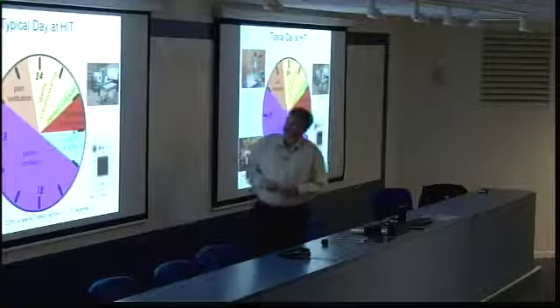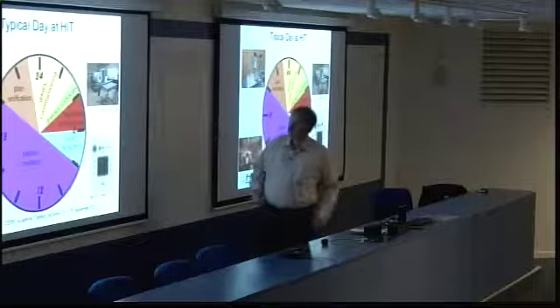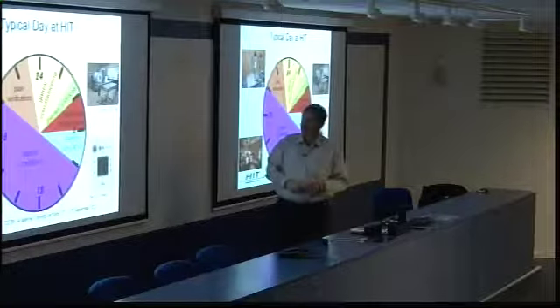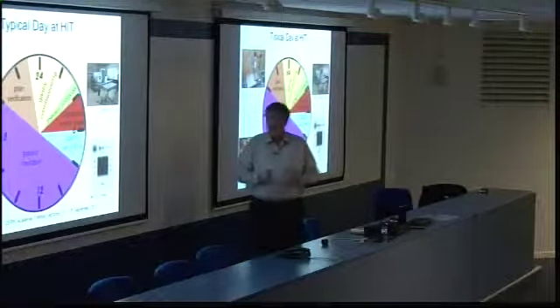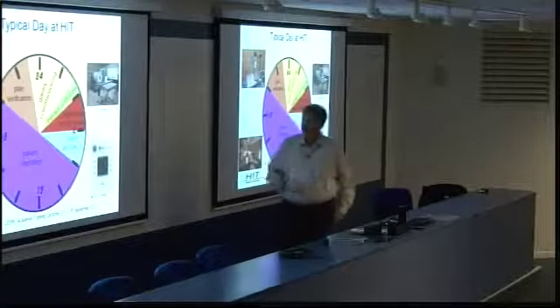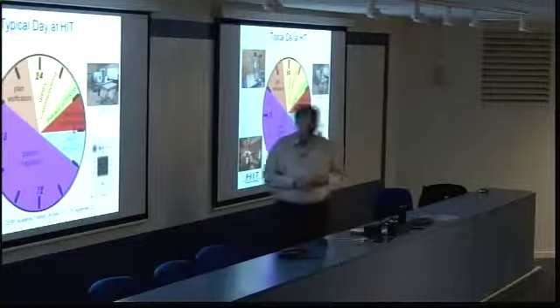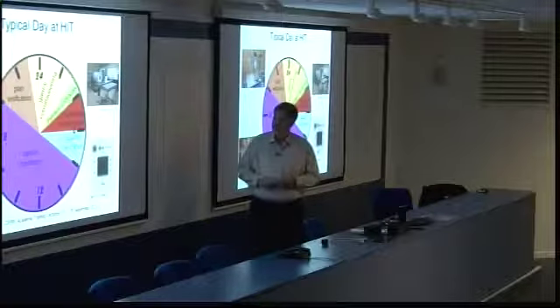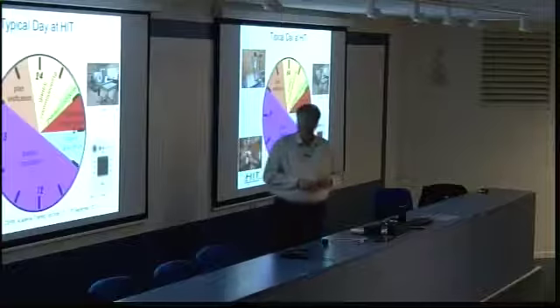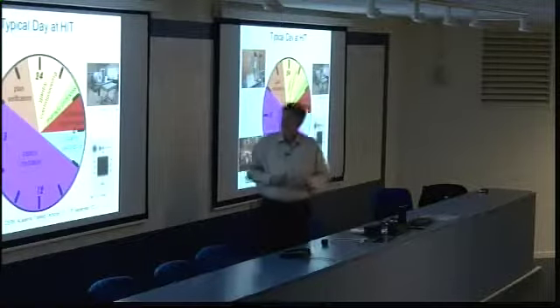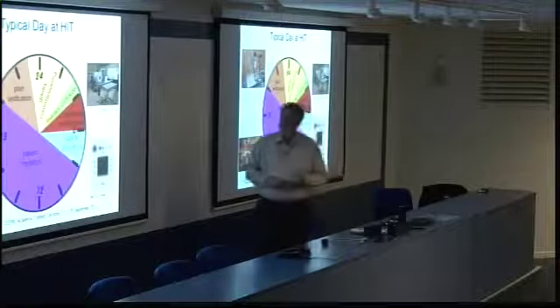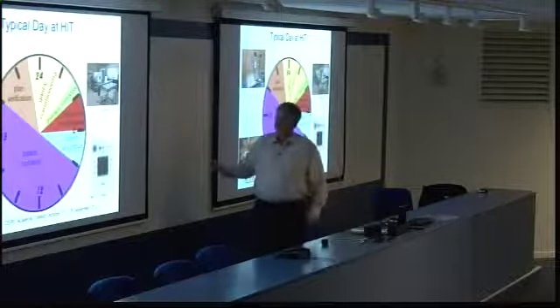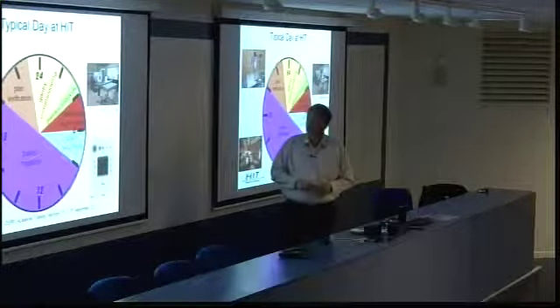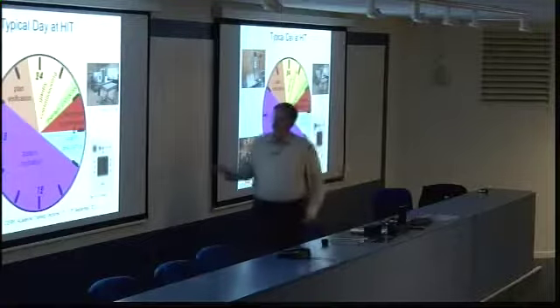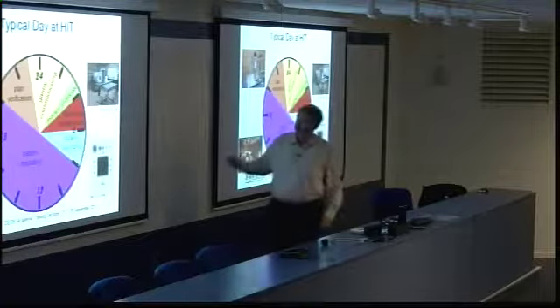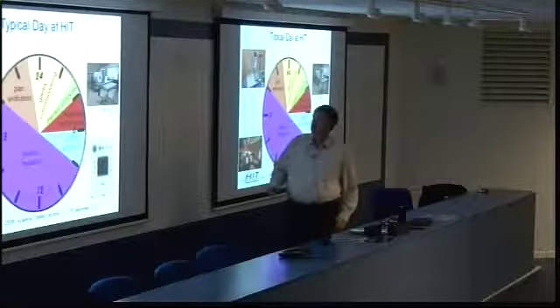What is it? You can see the measurement technique for that. This is a water basin with a stack of ionization chambers which measure the dose distribution point by point. Any plan that is applied to a patient is, at the moment, checked with this measurement technique, just to ensure that the plan is feasible, that it runs well, that the dose distribution is correct, and so on. I don't think that we will do that for all plans in future, so we are working on a software check that can do a lot of things beforehand, but nevertheless, plan verification is a very important thing.